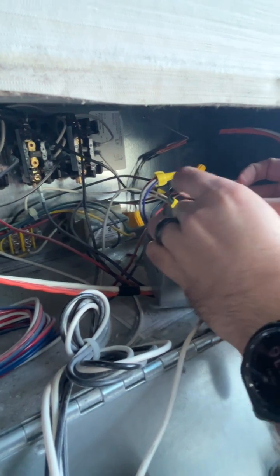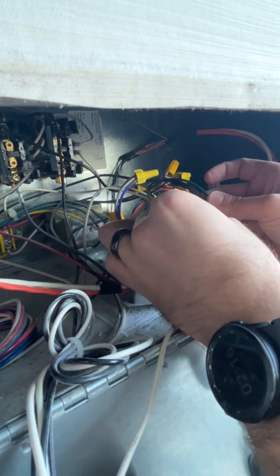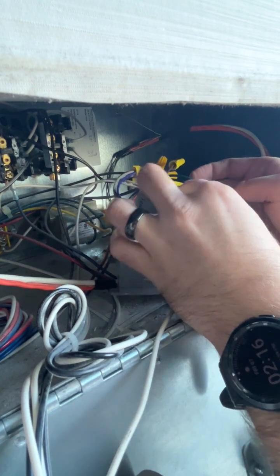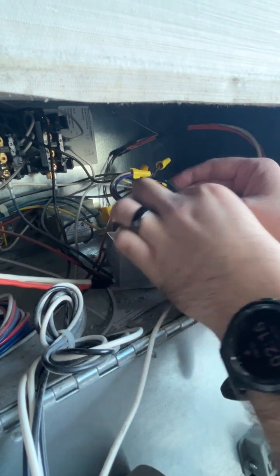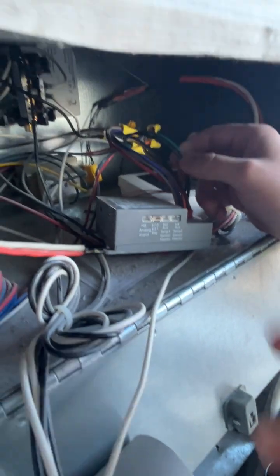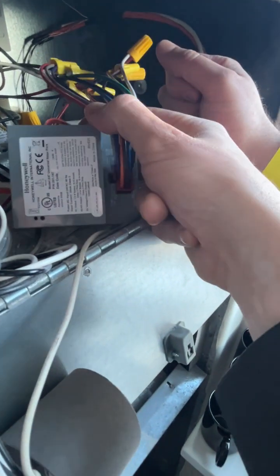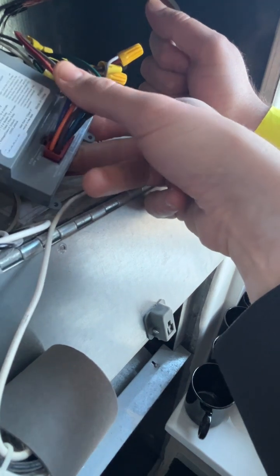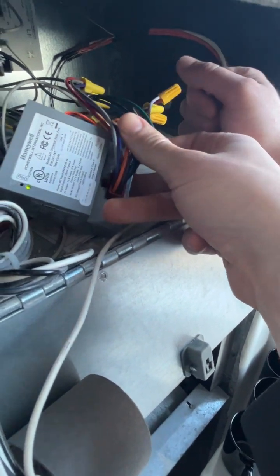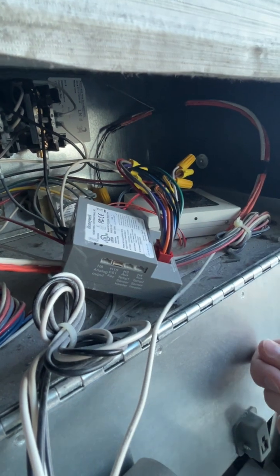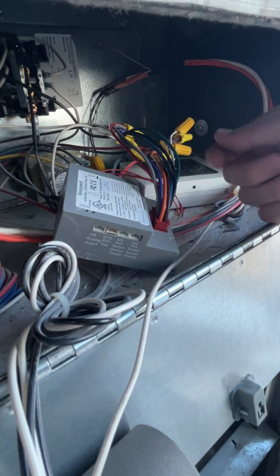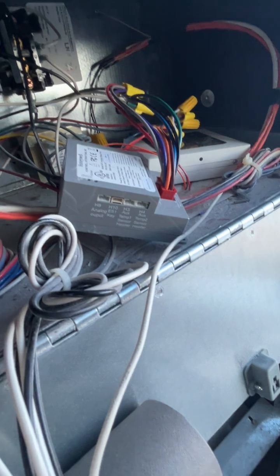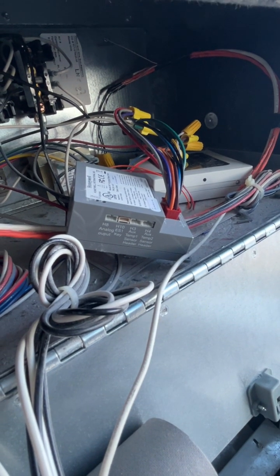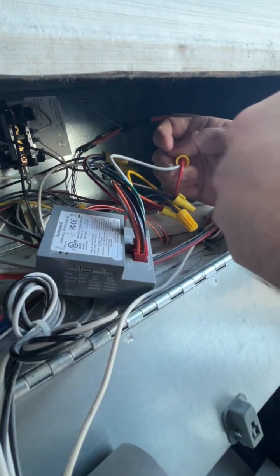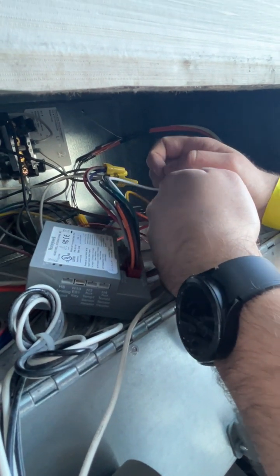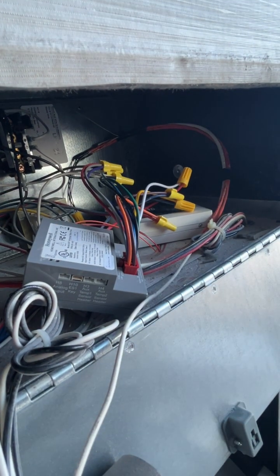White is heat. Yellow is cool. Black is your common and green is your ground. Those all get tied together. If you're metering, you set your multimeter to volts AC. You take your black probe and touch it to the ground of the unit, or you could also touch it to common. Then you take your red probe and check what you're trying to test. To test heat, put the red probe on the white wire, and you should see 24 to 27 volts AC somewhere in there.